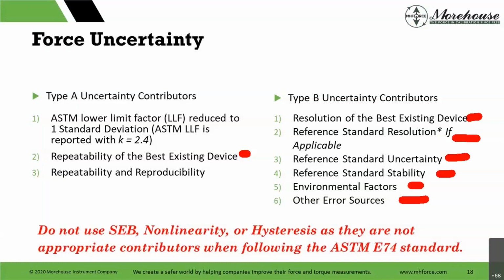NCSLI, I know it's their latest issue, has a great article on calibration drift and stability over time. Just fantastic. Highly recommend it if you haven't read it. So the note here is do not use, guess what? If you're doing an uncertainty budget properly, you probably don't need to use the manufacturer specification sheet with SEB, nonlinearity, or hysteresis.